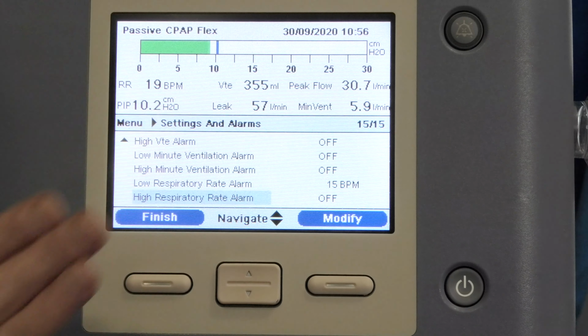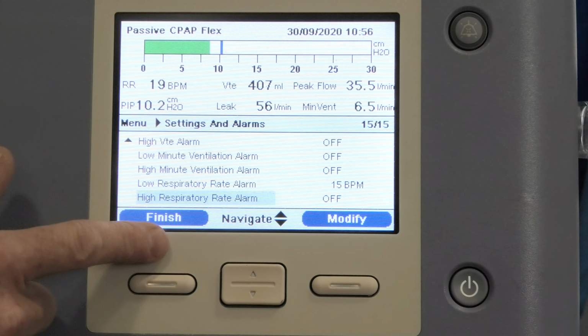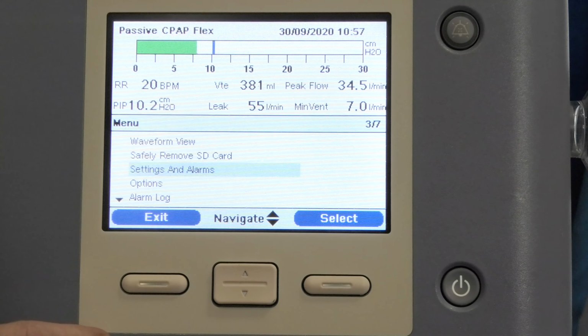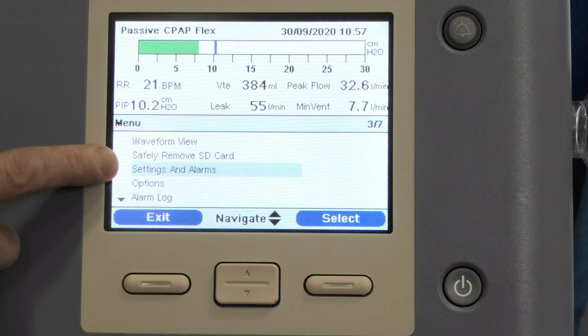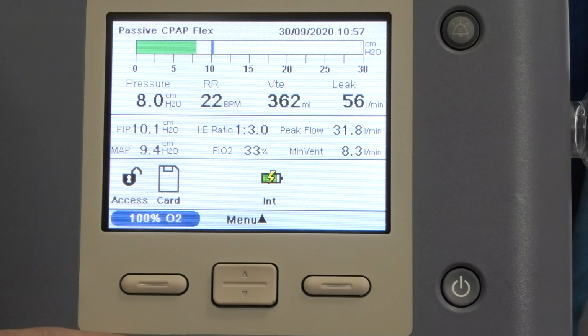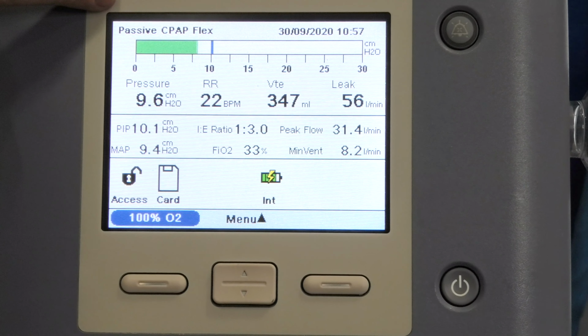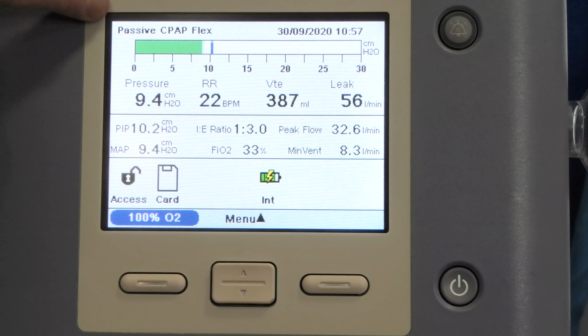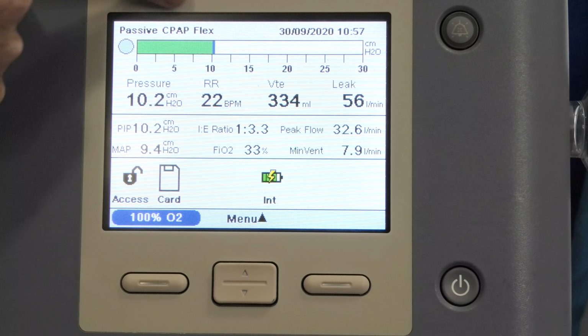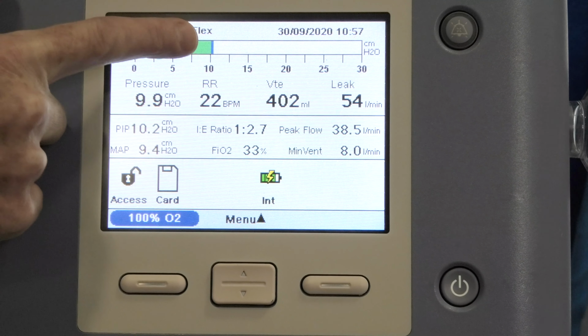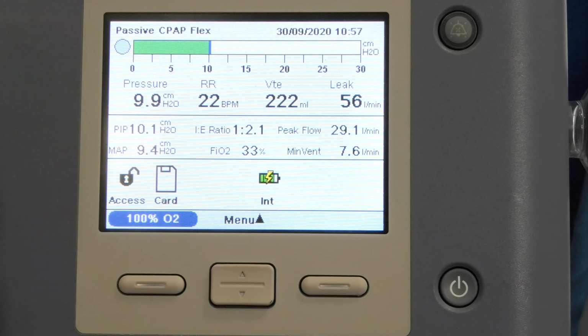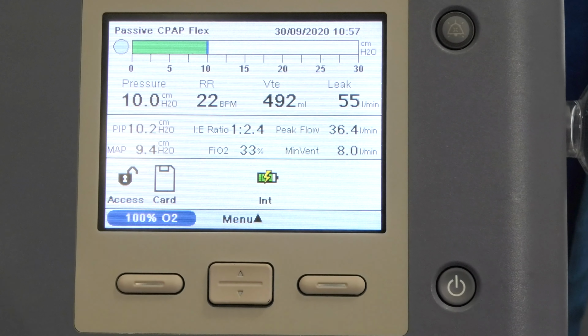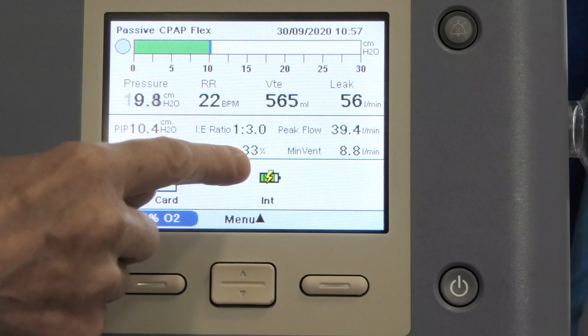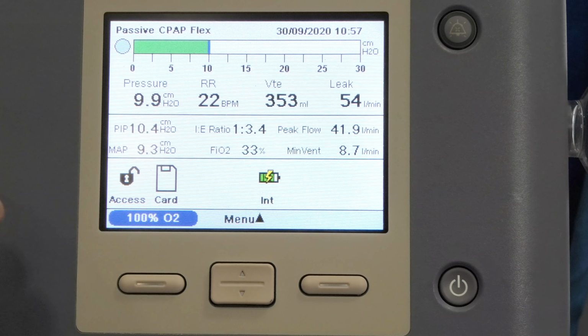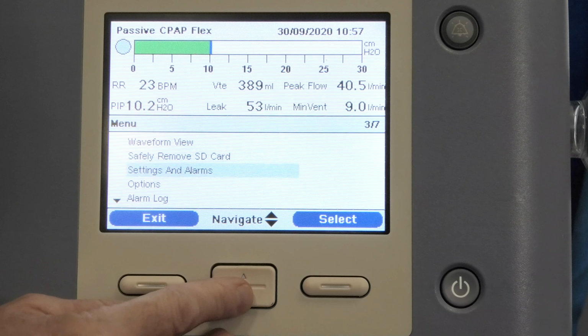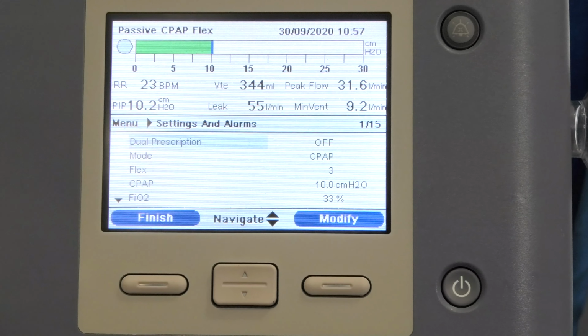Okay, so once I've finished changing all my settings, I literally just press finish and then it takes me back to the settings and alarm screen, and then I press exit. And then I'm away. I'm in passive. So passive is the type of circuit, so that means non-invasive ventilation. I'm in CPAP, and I've got flex. And it tells me the kind of pressures that I'm achieving and what my patient's respiratory rate is. I would probably amend my mask because that leak is a little bit too high, and it tells me how much oxygen the patient's on. If I want to change anything, back into menu, settings and alarms, and go through the system again.